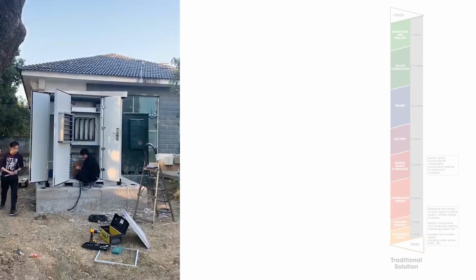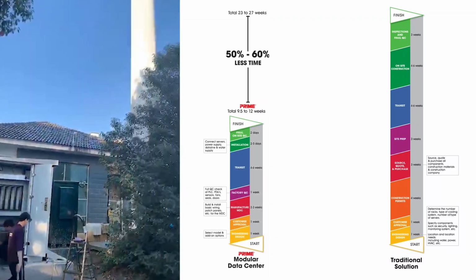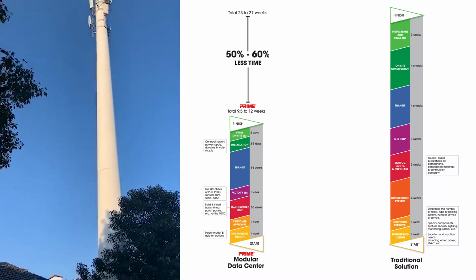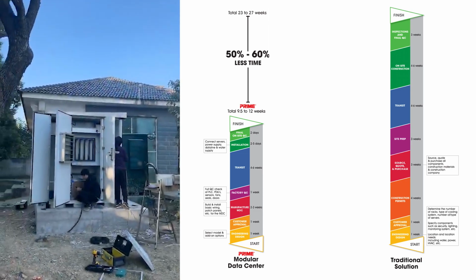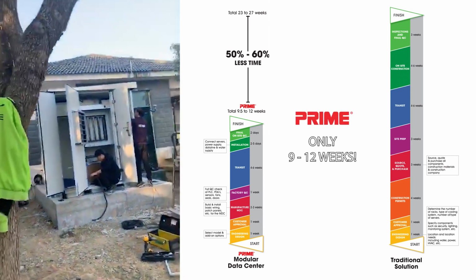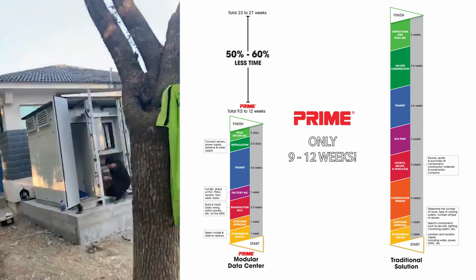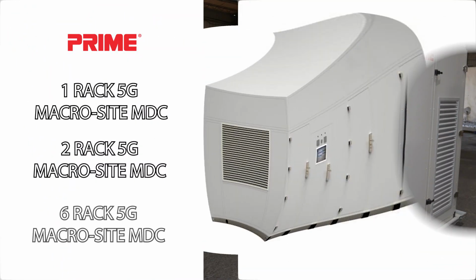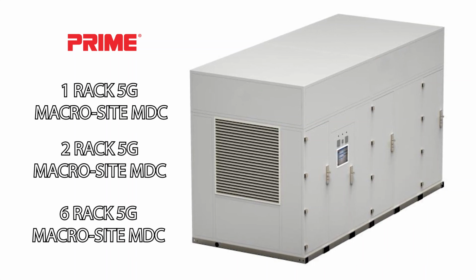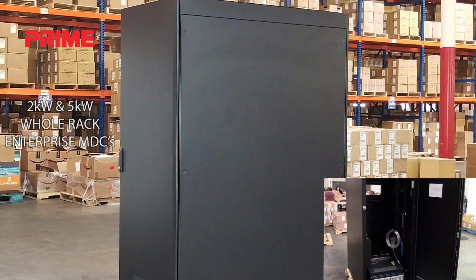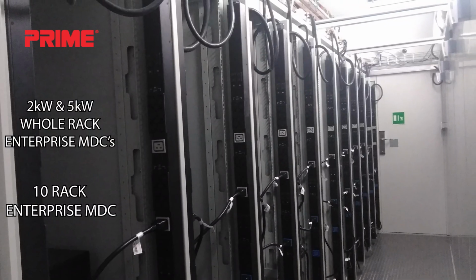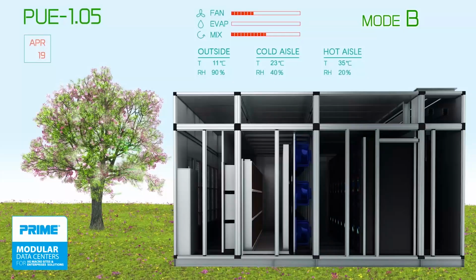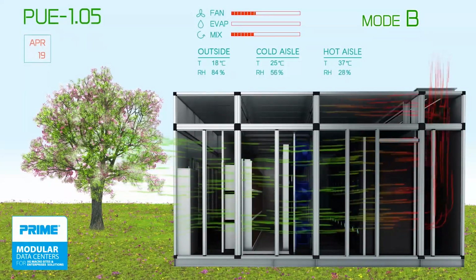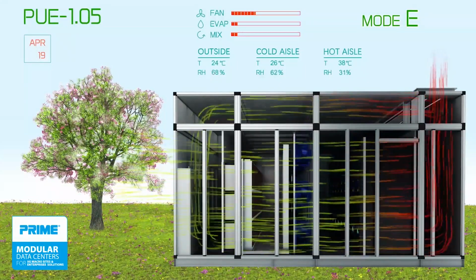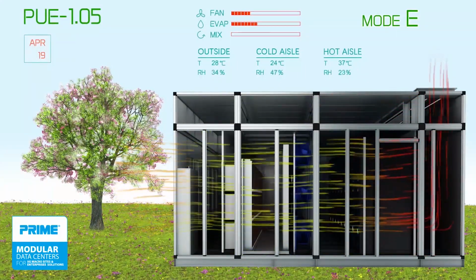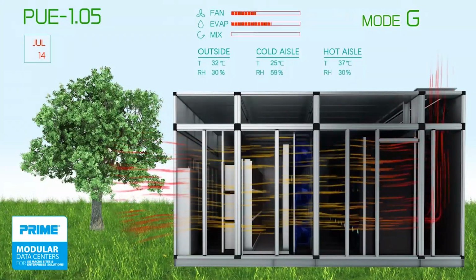Our 5G macrosite solutions, such as this one, can be deployed at least 50% faster than traditional built-from-scratch solutions. From the start of the project to deployment, it's only 9 to 12 weeks as compared to about 27 weeks for more traditional solutions. We have prefabricated 1, 2, and 6-rack 5G macrosite models. All are made with the same basic components. We also have whole rack and up to 10 rack self-contained enterprise solutions. The greatest cost savings in energy efficiency comes from the natural air cooling system with supplemental evaporative cooling that comes standard with each Prime MDC. Let's take a closer look.